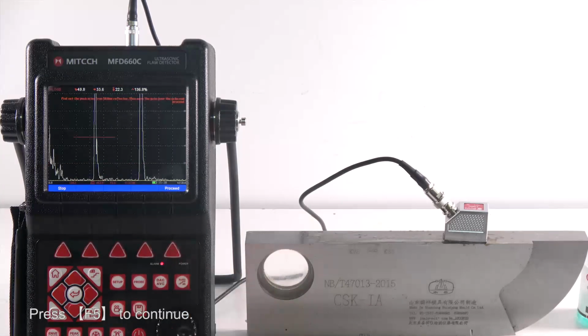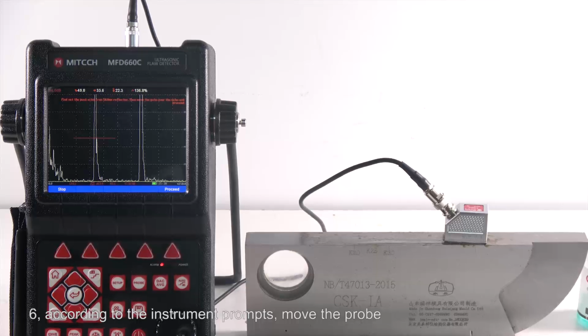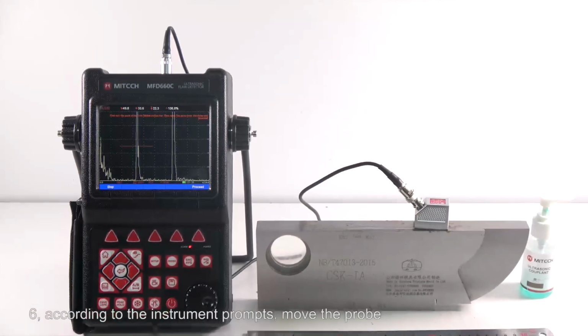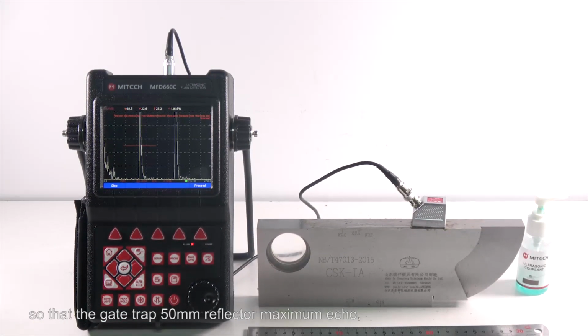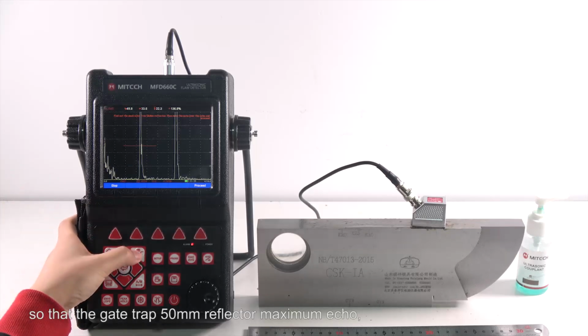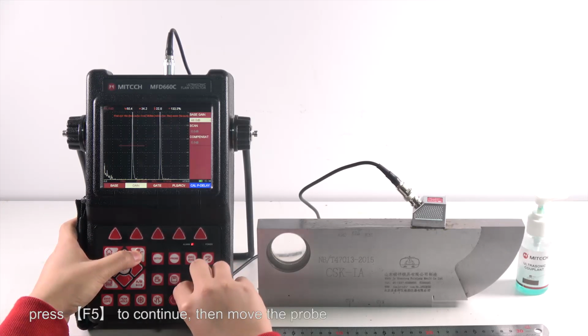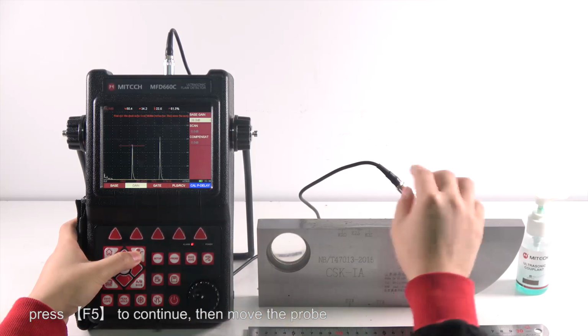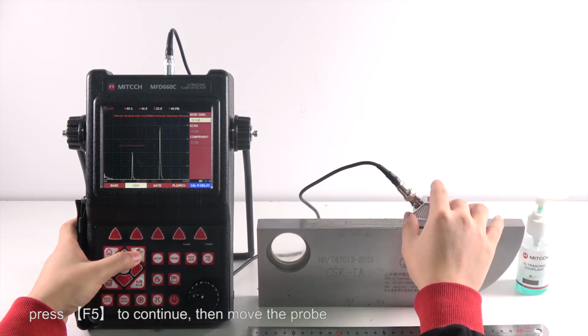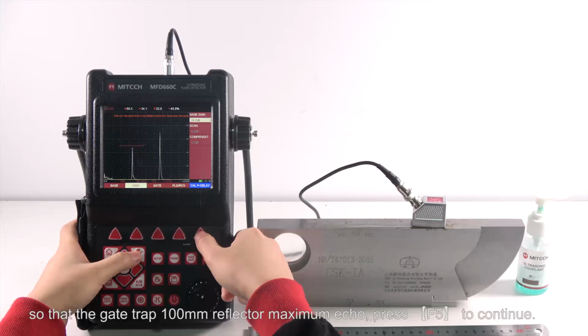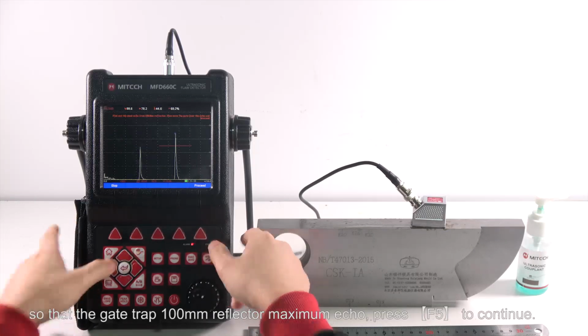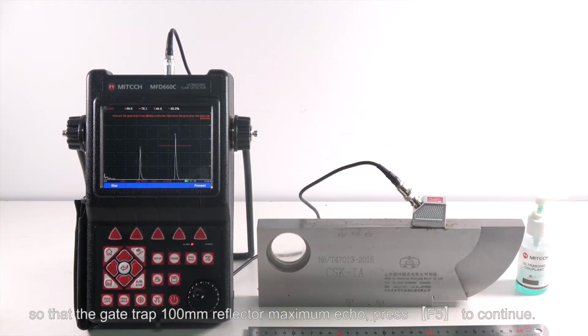Press F5 to continue. According to the instrument prompts, move the probe so that the gate traps the 50 mm reflector's maximum echo. Press F5 to continue, then move the probe so that the gate traps the 100 mm reflector's maximum echo. Press F5 to continue.